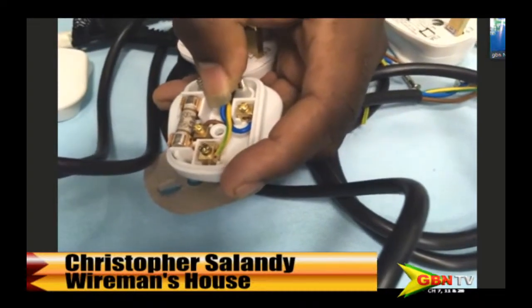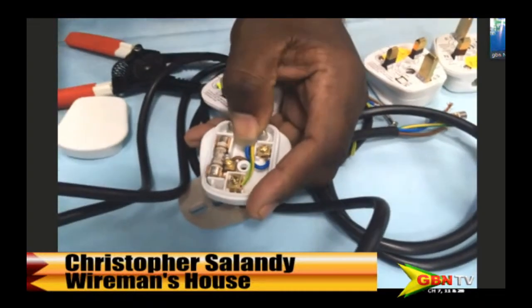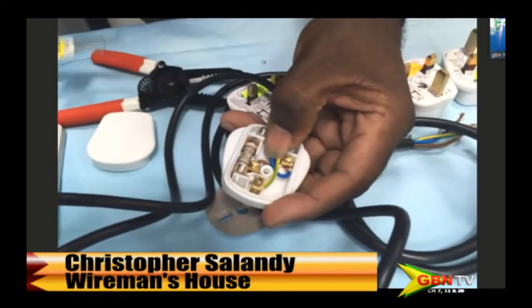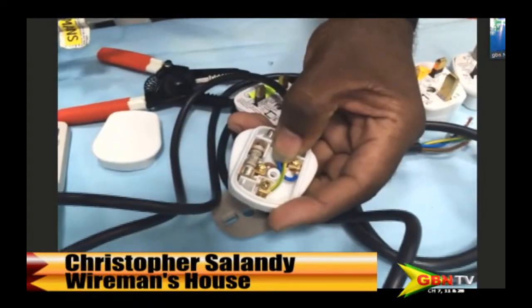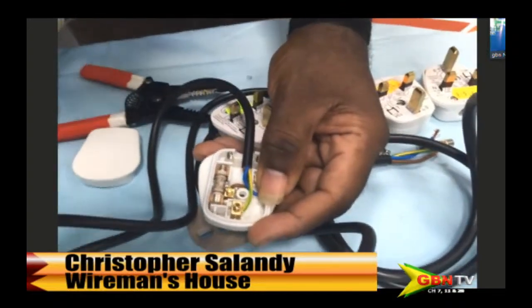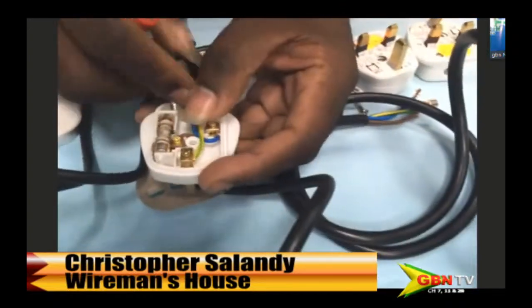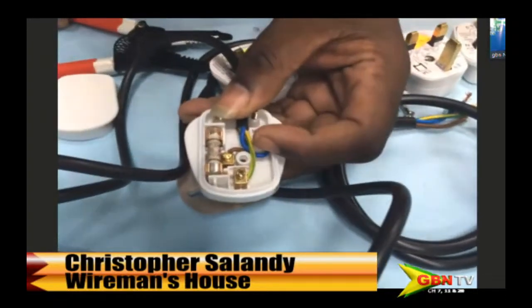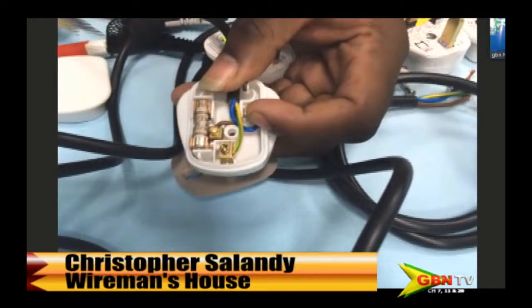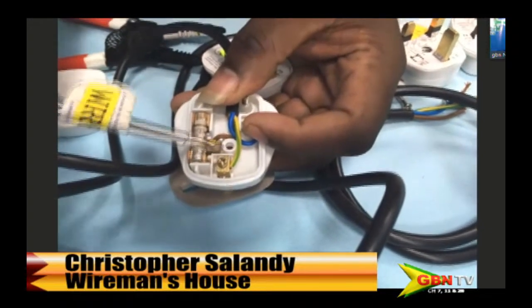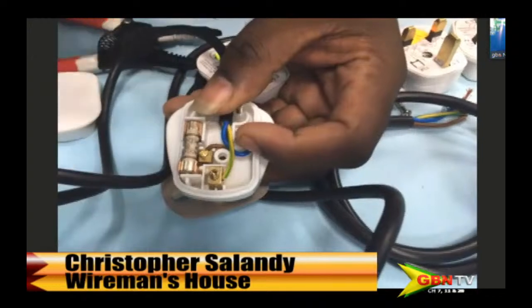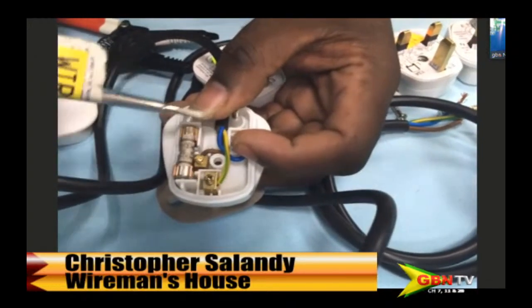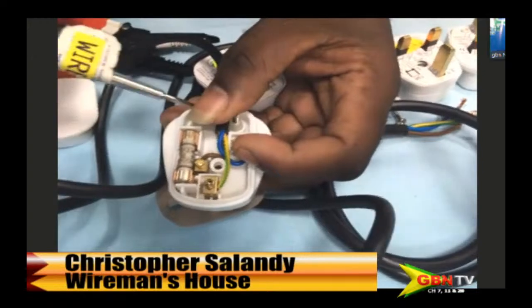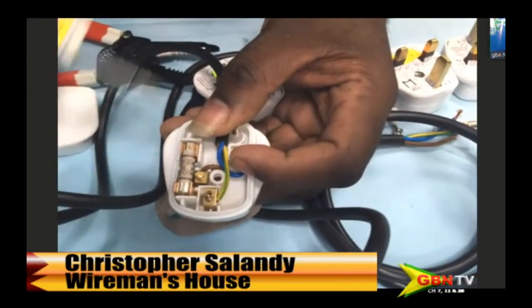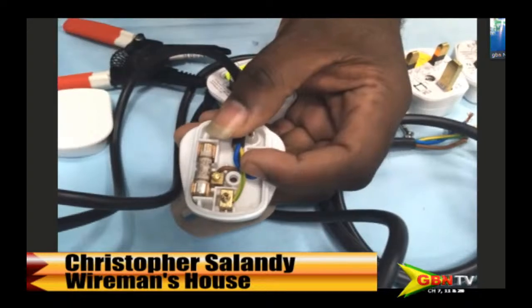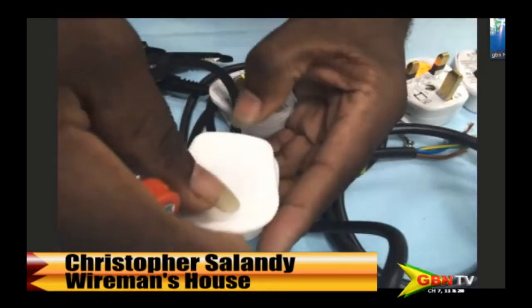It's a culture we've gotten into. You know, we run out of fuses, so even for regular homemade adapters, we just get a piece of foil paper and bridge it, telling ourselves it's fine. But that will cause a problem, actually cause a fire, because the current will be continuously flowing back and forth in the plug, and that will cause the terminals to heat up, melt the plug, and eventually start a fire. So that is an accident waiting to happen, sooner rather than later.